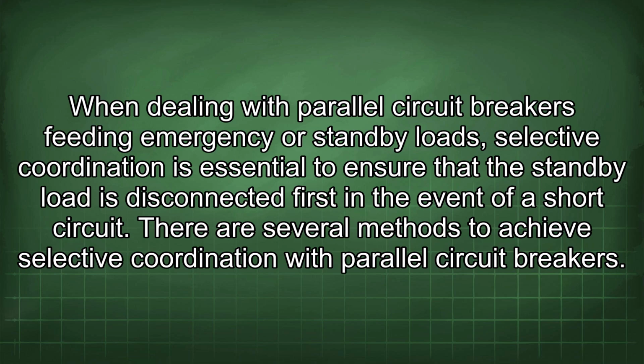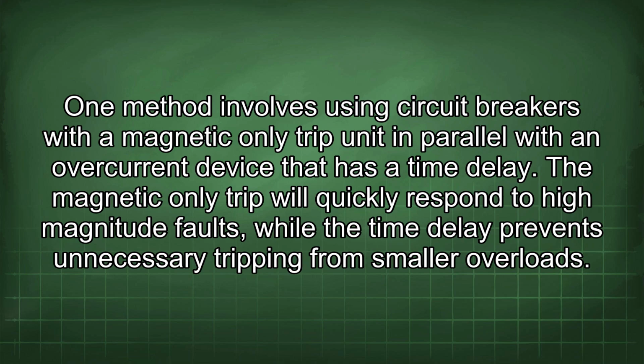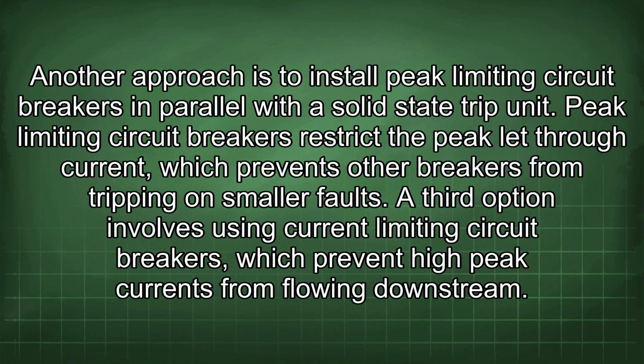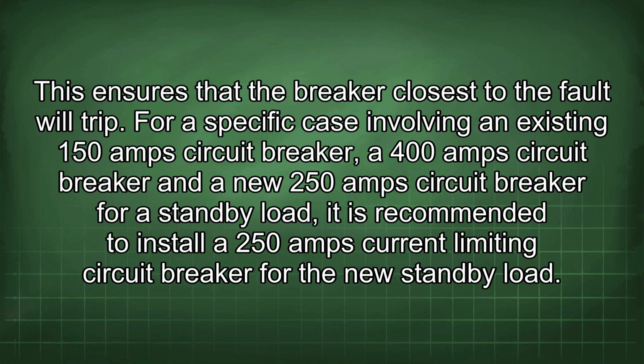There are several methods to achieve selective coordination with parallel circuit breakers. One method involves using circuit breakers with a magnetic-only trip unit in parallel with an overcurrent device that has a time delay. The magnetic-only trip will quickly respond to high-magnitude faults, while the time delay prevents unnecessary tripping from smaller overloads. Another approach is to install peak-limiting circuit breakers in parallel with a solid-state trip unit. Peak-limiting circuit breakers restrict the peak let-through current, which prevents other breakers from tripping on smaller faults. A third option involves using current-limiting circuit breakers, which prevent high peak currents from flowing downstream. This ensures that the breaker closest to the fault will trip.